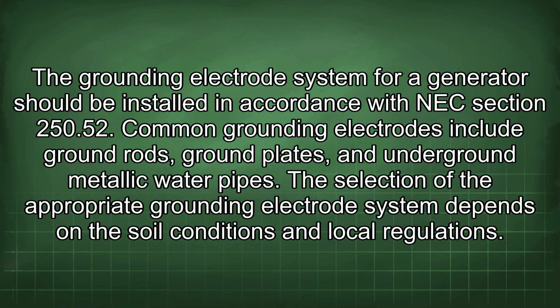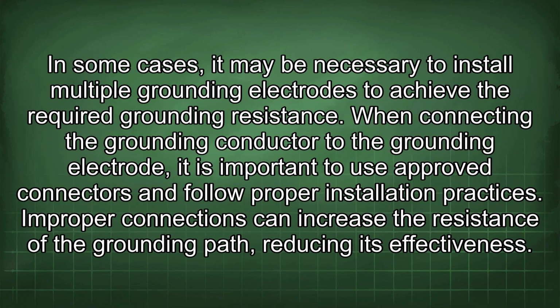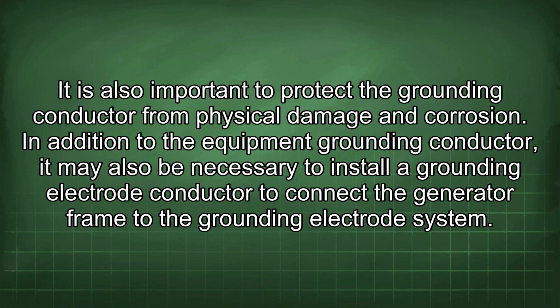The selection of the appropriate grounding electrode system depends on the soil conditions and local regulations. In some cases, it may be necessary to install multiple grounding electrodes to achieve the required grounding resistance. When connecting the grounding conductor to the grounding electrode, it is important to use approved connectors and follow proper installation practices. Improper connections can increase the resistance of the grounding path, reducing its effectiveness. It is also important to protect the grounding conductor from physical damage and corrosion.